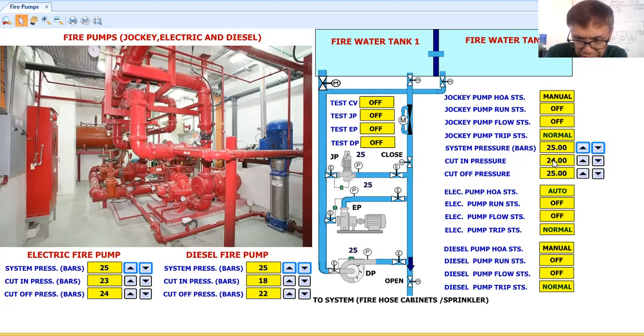Then we are monitoring the system pressure. Okay, now my system pressure here is in bars. Some are in PSI. Okay, so here I am just monitoring it in bars. Now this is just fictitious values. Okay, I'm just going to give you an idea how these pumps will start. Now, likewise in my electric pump, I have the same points: hand-off-auto, run, flow, trip. Then for the diesel, the same points.